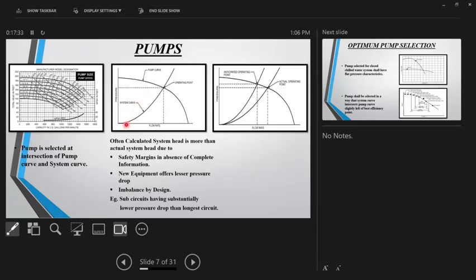A system curve is nothing but how your system behaves. Now, for a fixed system, if you increase the flow rate, obviously the pressure drop is going to increase, correct? For a pump, it is the opposite. For the system curve, it's opposite. If you go on increasing the flow, the resistance experienced by the system is going to increase. So at this flow, the resistance was, let's say, this. If you increase the flow, the resistance is going to increase. So that's how we see these two diverse kinds of performance envelopes. Now, obviously, we all know the pump system is going to operate where these two curves meet each other, and that is known as the operating point.